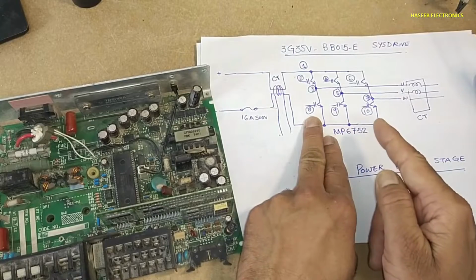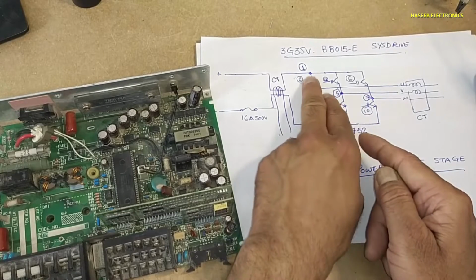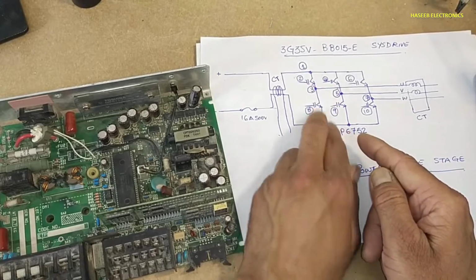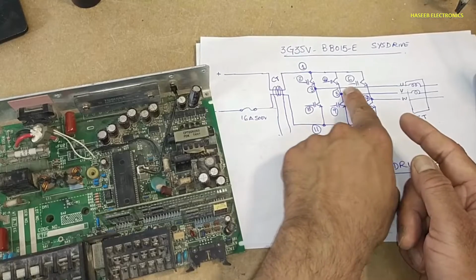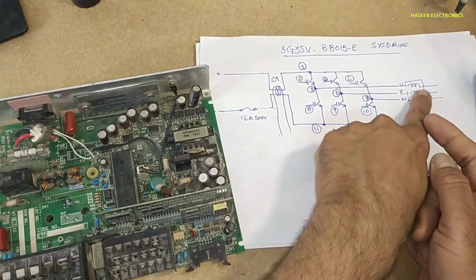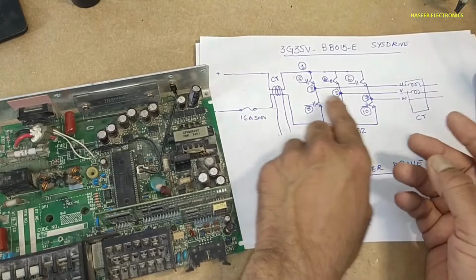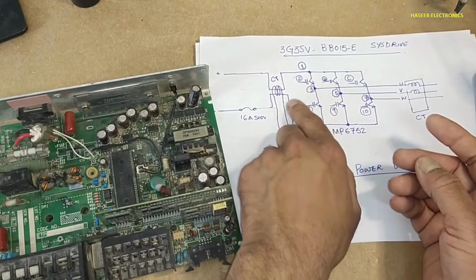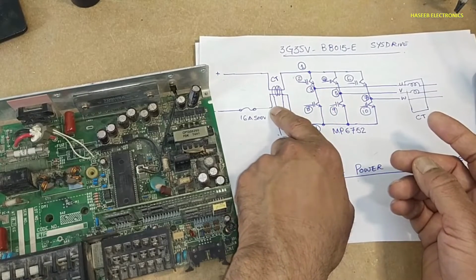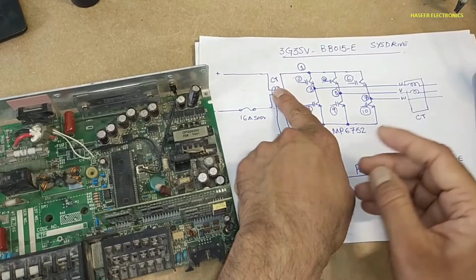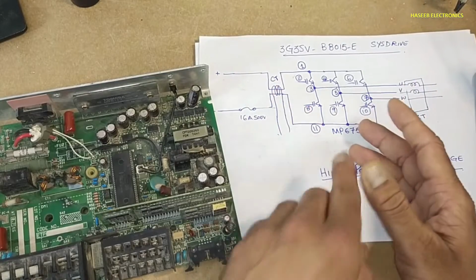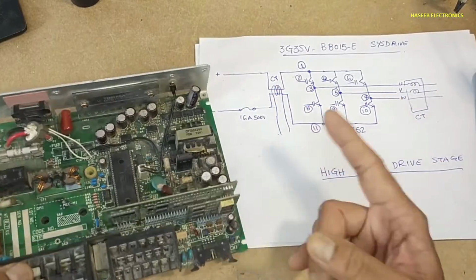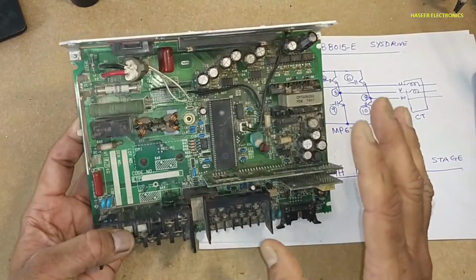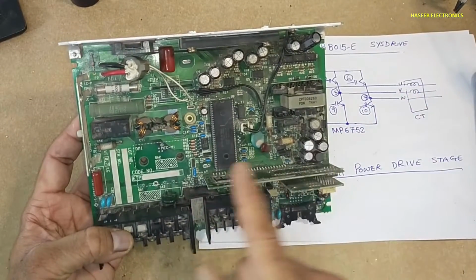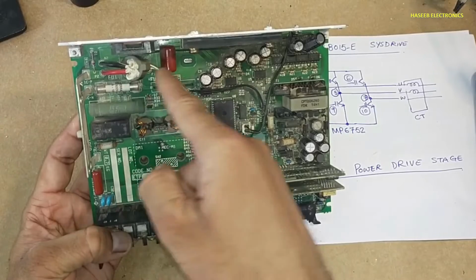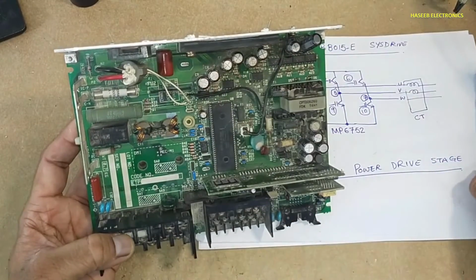because it is the high power switching area. If any IGBT is short circuited, any pair is short circuited, or any one output line is short circuited, that will cause a huge amount of current to be drawn. If there is an overcurrent condition, it will damage everything. To protect from any unexpected damage, it will monitor the current.